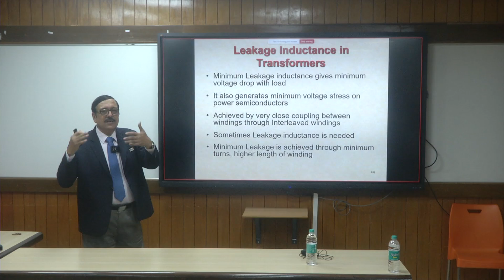Thyristor rectifiers are almost out from normal applications, but they are going to come in once again with hydrogen rectifiers. All the submarine battery chargers that we make, megawatts, are all thyristor because they are rugged. Everybody wants rugged equipment. Efficiency-wise they are not really bad. Most of the efficiency loss there goes because of the transformer and the chokes. But they are rugged. They give us less than 5% THD on the input side because we have 24 pulse rectifiers, and that's more suitable for such large power applications.